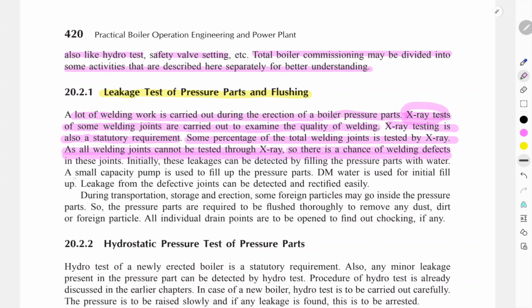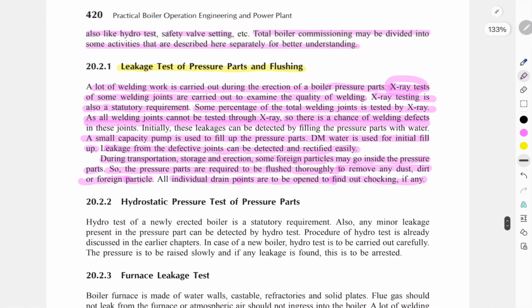Understood? A small capacity pump is used to fill up the pressure parts. DM water is used for initial fill up. The leakage from a defective joint can be detected and rectified easily. During transportation, storage and erection, some foreign particles may go inside the pressure parts, so the pressure parts are also required to be flushed thoroughly. To remove any dust, dirt and foreign particles, the individual drain points are to be opened. Find out if there is any choking anywhere. So this is what should be done in the leakage test.